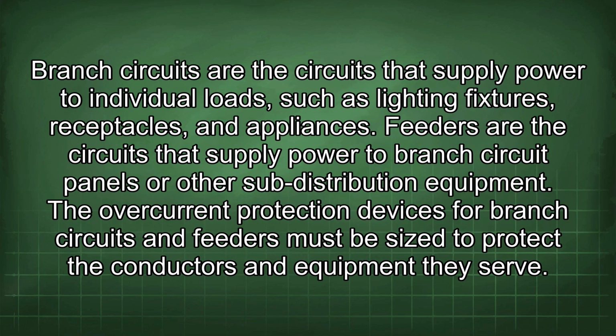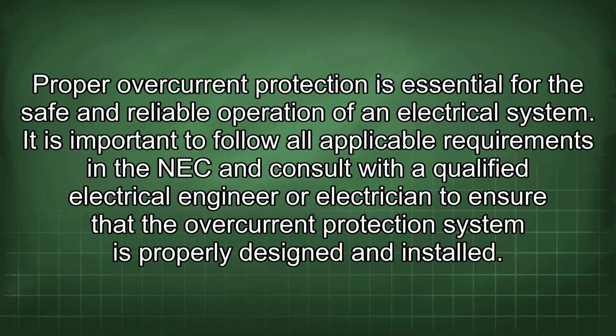Branch circuits are the circuits that supply power to individual loads such as lighting fixtures, receptacles, and appliances. Feeders are the circuits that supply power to branch circuit panels or other sub-distribution equipment. The overcurrent protection devices for branch circuits and feeders must be sized to protect the conductors and equipment they serve. Proper overcurrent protection is essential for the safe and reliable operation of an electrical system. It is important to follow all applicable requirements in the NEC and consult with a qualified electrical engineer or electrician to ensure that the overcurrent protection system is properly designed and installed.